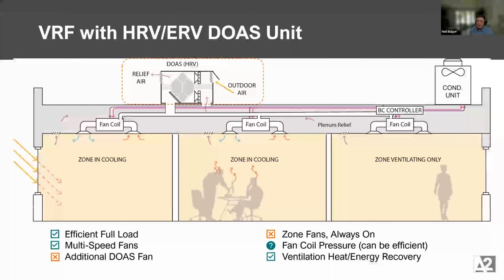And you could definitely consider whether you would change the curves. I guess it's probably better to think of it this way: if you have a DOAS unit that really can control moisture, and it's a DX DOAS, let's say it's able to dehumidify and heat the air as needed, you certainly in the software could change the fan coil's sensible heat ratio and say it does more sensible heat and less latent. You might see some differences in performance, but it's definitely hard to change. If you were to re-engineer the curves, I think that would take a concerted effort and perhaps be more than one project. It would need to be more manufacturer specific.